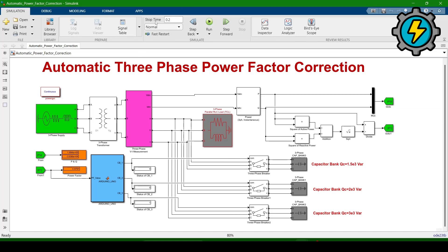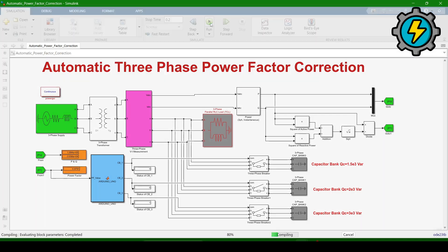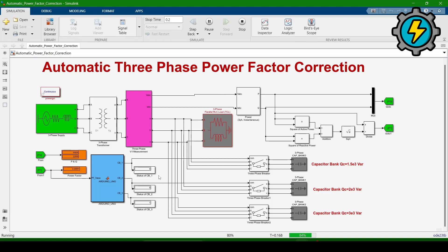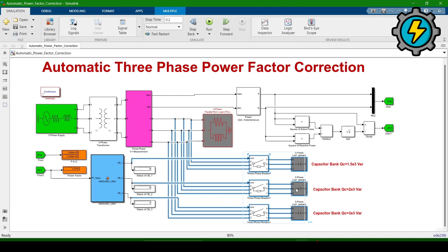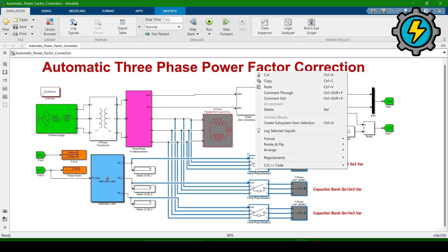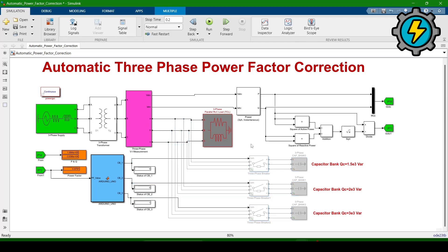The simulation time is set to 0.2 seconds. Running the full simulation shows the power factor is 0.9791. Now, to analyze how the power factor is improved, we will comment out the three capacitor banks — commenting out means these blocks will be eliminated from the simulation. Running without the capacitor banks shows the power factor is 0.582, which is very low.